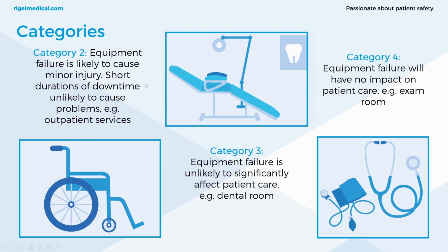There's category 2. Now this is equipment failure is likely to cause minor injury. A good example of this is outpatient services. Category 3, so as we move lower through the risk values, then equipment failure is unlikely to significantly affect patient care, e.g. a dental room. And then category 4 is the lowest risk, and a good example of this is an exam room. Now it's important to note that the examples below may vary depending on the actual impact and risk. It's always up to the facility to categorise these types of areas.